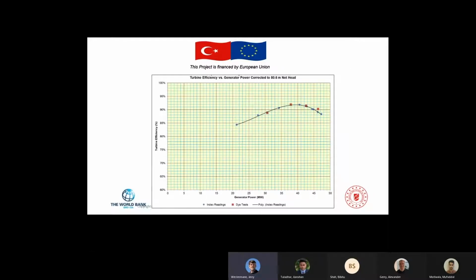Here you see a typical result. We combine both index testing, and you see the index test readings here, the blue diamonds, and we have 4 dye tests in this case, and the dye tests we're using to effectively set the peak of this curve, okay? Because with the index test by itself, we're not measuring the exact flow or the absolute flow. We're only measuring a relative flow with the index test.